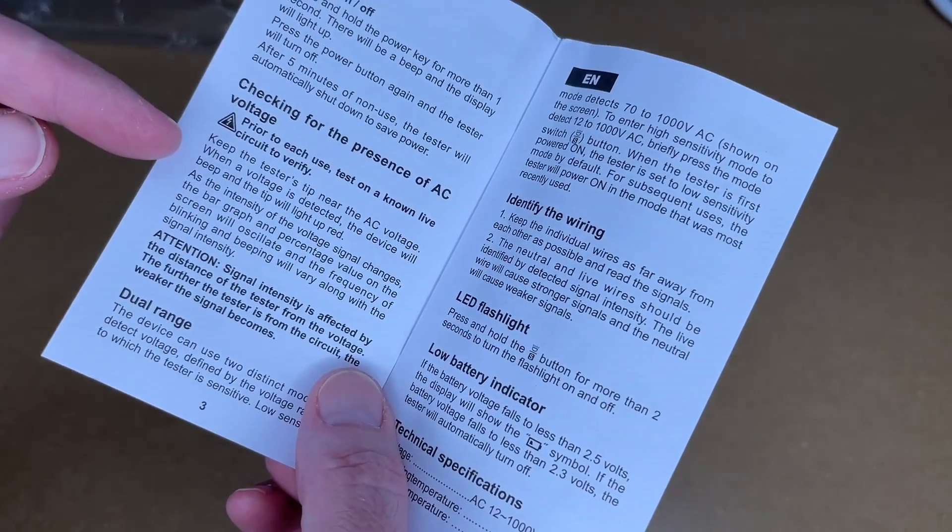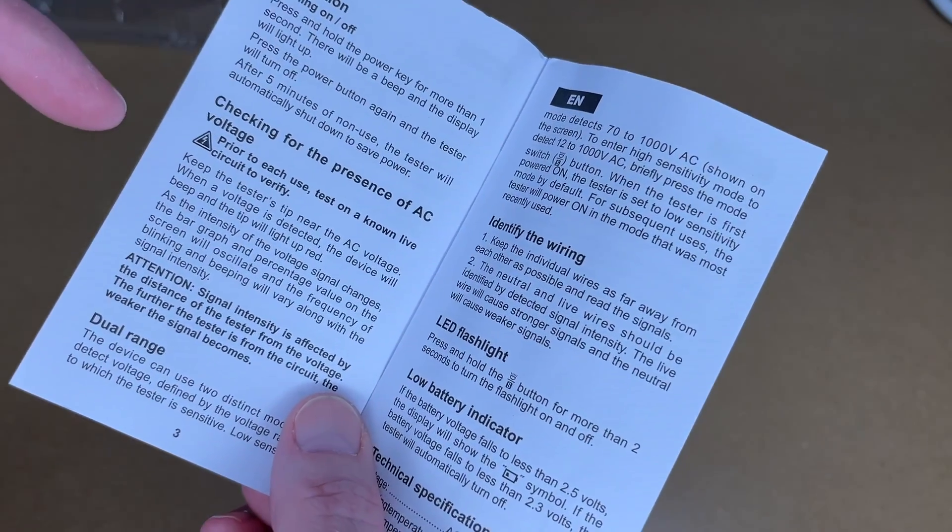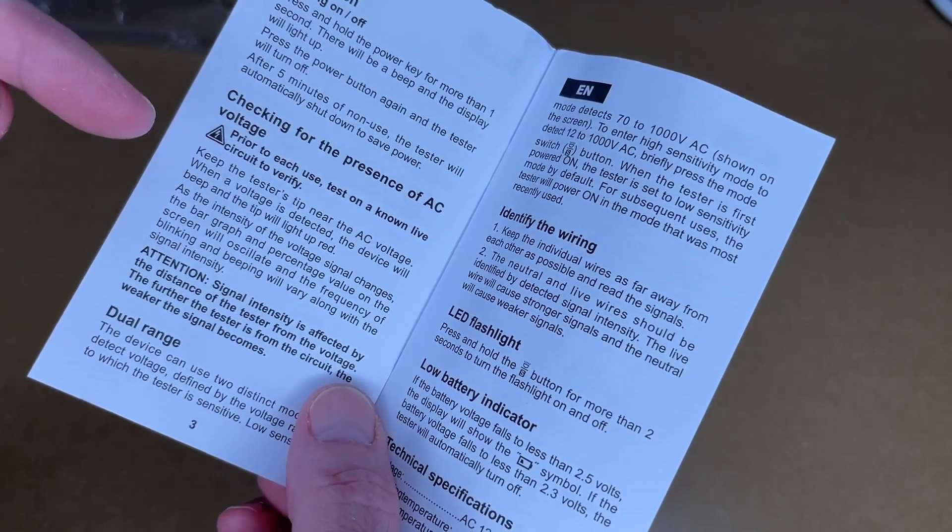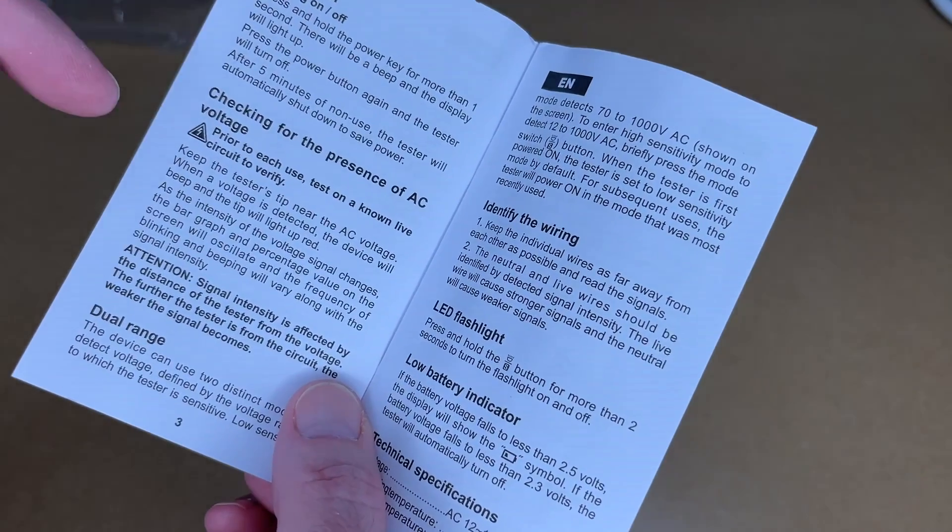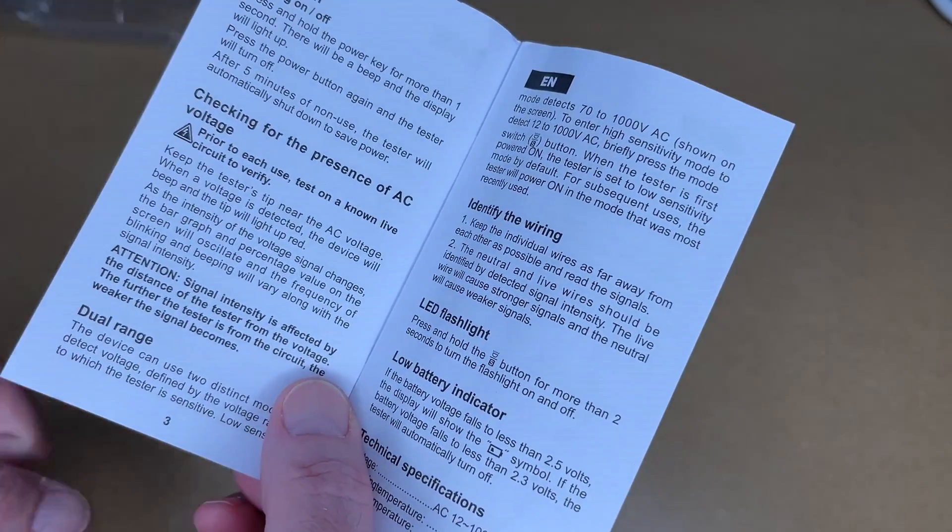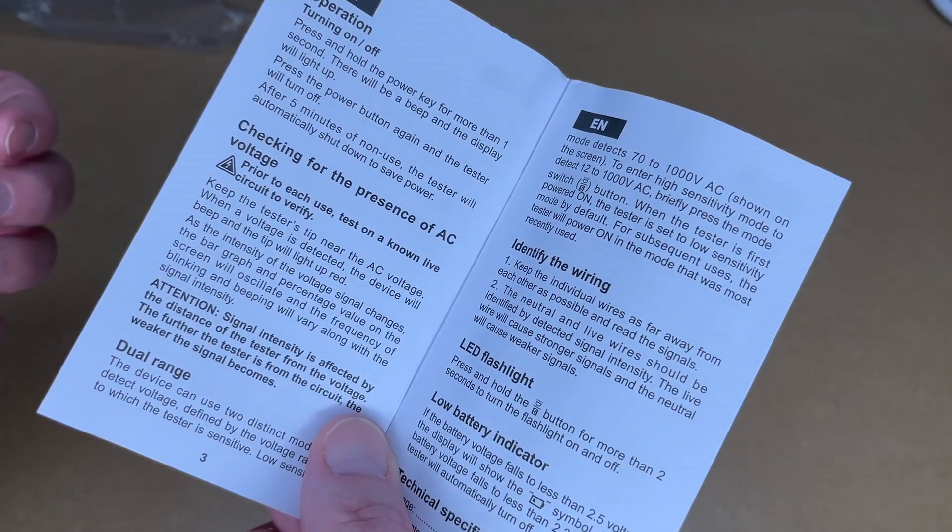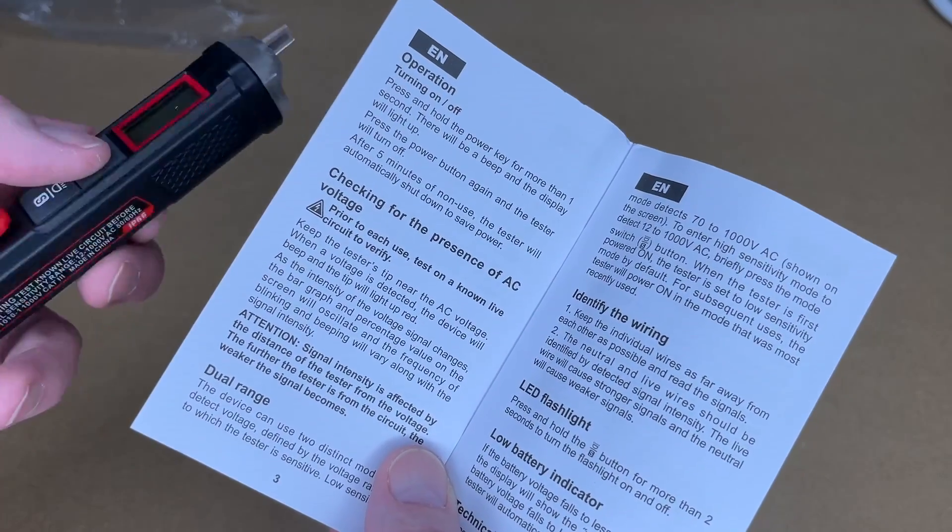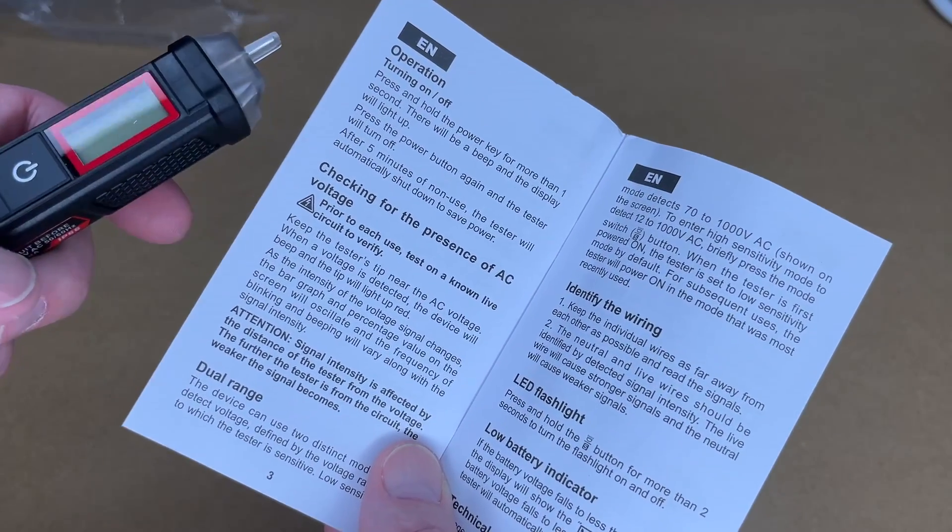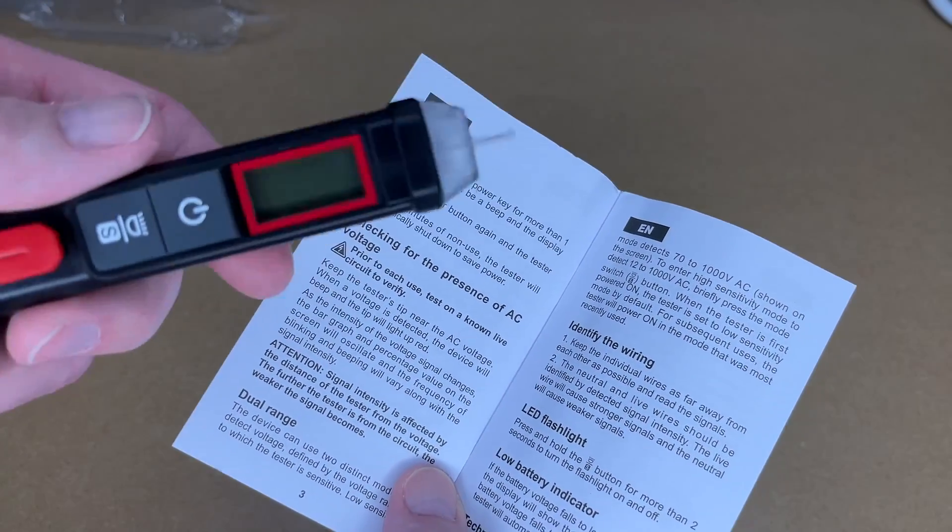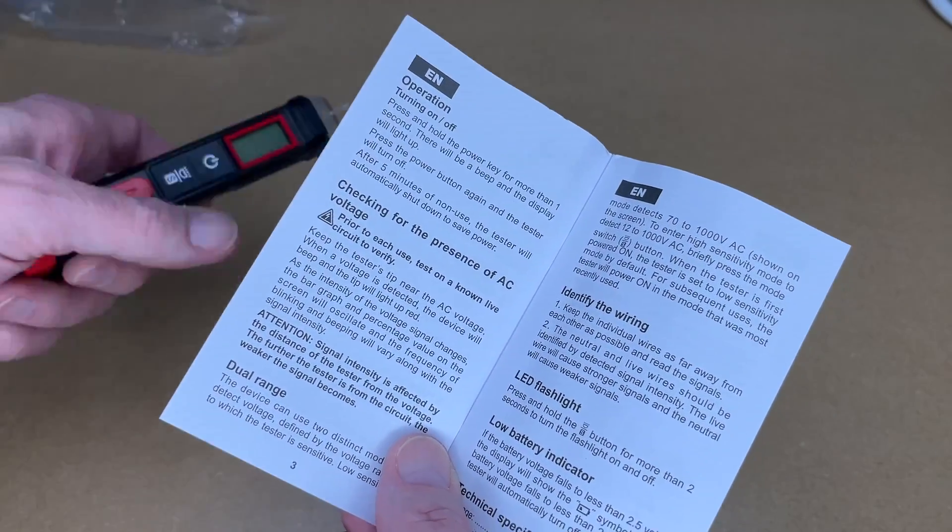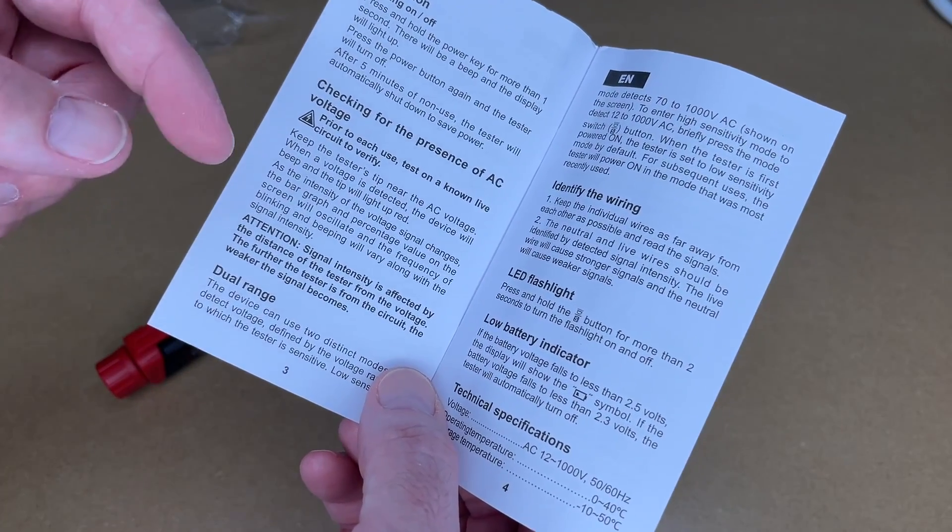This talks about detecting the presence of AC voltage. And this is an important step. You want to test it on a known live circuit to verify that it's working. So say you shut off the circuit to an outlet. You could take this and you can test it. But you should test it on an outlet that you know works first to make sure this is working properly. And I'm just going over the basics of this.